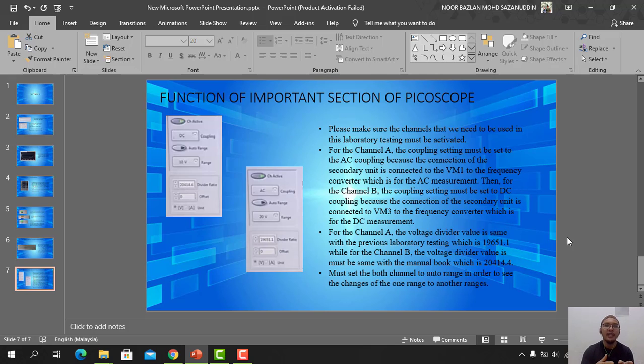We must also make sure that the voltage divider ratio of the secondary resistor unit, 20414.4, is set for channel B, while for channel A, the AC measurement divider ratio must be set the same as the previous laboratory testing, which is 19651.1. Lastly, we must set both channels to auto range.